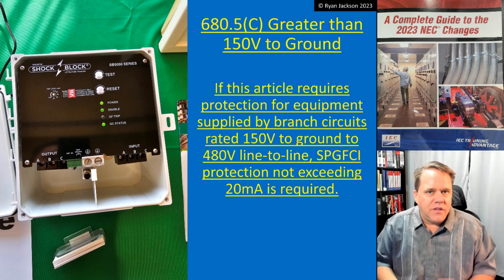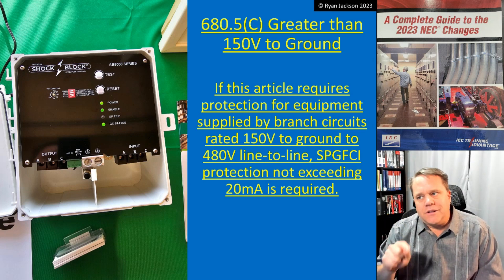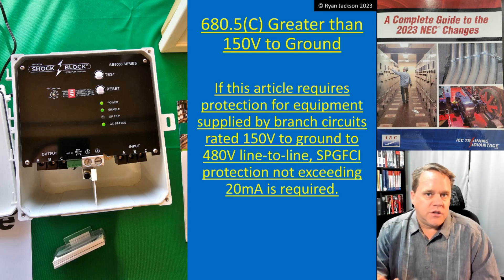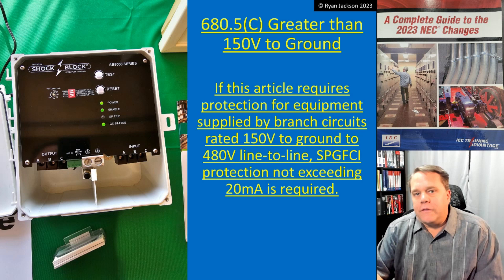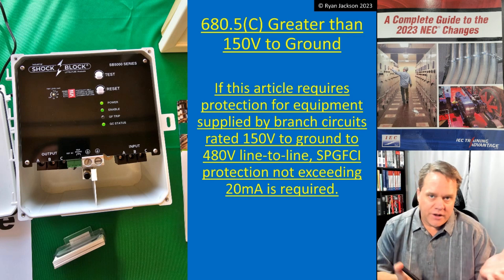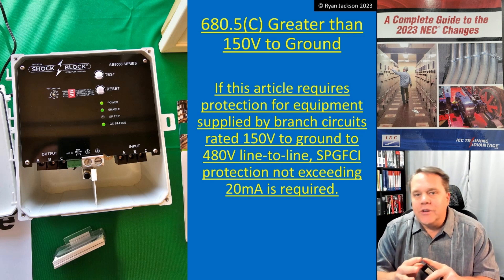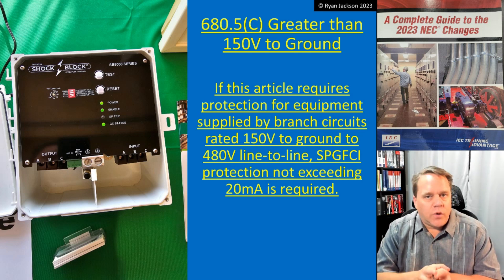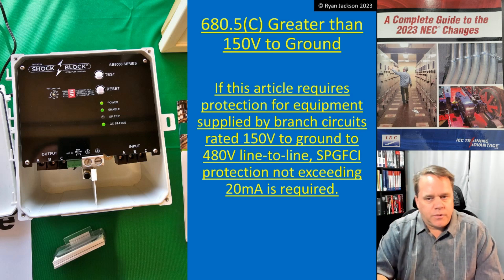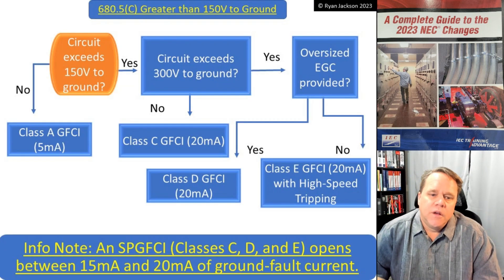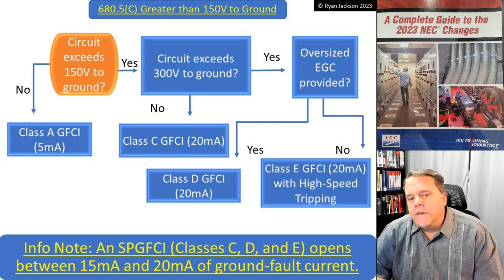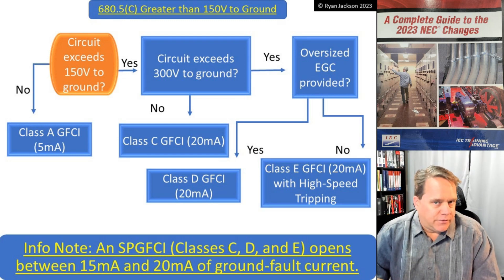Until now, we acknowledged the risk and knew the hazard but didn't really have any good ways to alleviate it. So in the 2023 code, for those higher-voltage motors and equipment, we can use special purpose GFCI. There's an informational note added that says an SP GFCI — Class C, D, or E — opens between 15 milliamps and 20 milliamps of ground fault current.